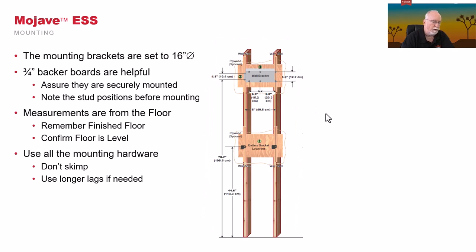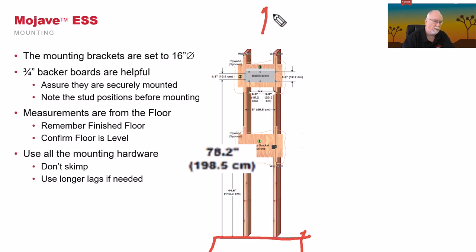So, important things to note is that the first height is 78.2 inches above the ground. So again, our floor needs to be level. So we're going to make sure our floor is level. We're going to make sure the proper height is available in the ceiling. And then we're going to put our mounting bolt, our first one, at 78.2 inches above the ground. Then we're going to go 4.1 inches above that. We're going to drill in our second one. At that point, probably use a level, make sure that it's all set to go. And we'll actually walk through those steps.